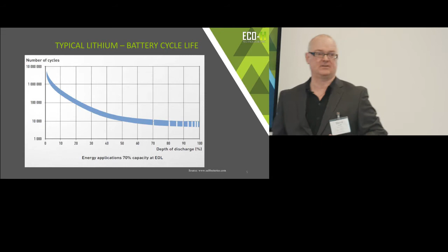We dragged the oil and gas industry kicking and screaming into the 21st century with energy storage. We were told we'd never get into oil and gas because everybody wants big black smoke. Oil rigs on land and gas rigs, they're designed for peak power. When someone designs a rig, they work out that in the worst case scenario, if everything's switched on, you'll need 4 megawatts of power, so there'll be 4 one-megawatt generators there, all on, all needed. The average power might be 800 kilowatts, but you still design for 4 megawatts. That's the philosophy, that's the mindset.